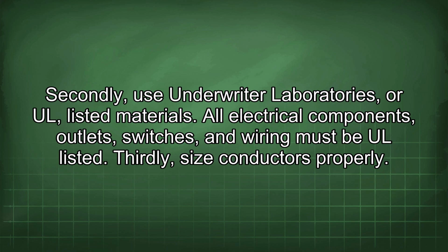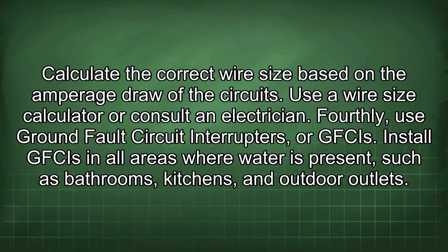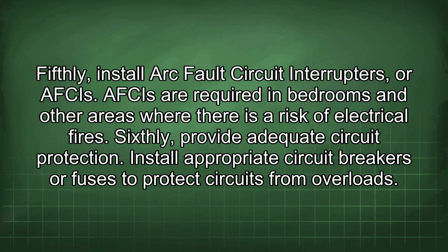Thirdly, size conductors properly. Calculate the correct wire size based on the amperage draw of the circuits. Use a wire size calculator or consult an electrician. Fourthly, use ground fault circuit interrupters, or GFCIs. Install GFCIs in all areas where water is present, such as bathrooms, kitchens, and outdoor outlets. Fifthly, install arc fault circuit interrupters, or AFCIs. AFCIs are required in bedrooms and other areas where there is a risk of electrical fires.